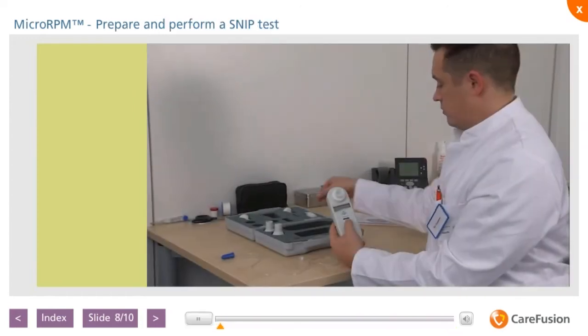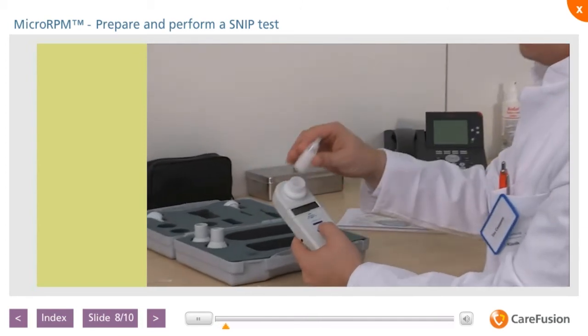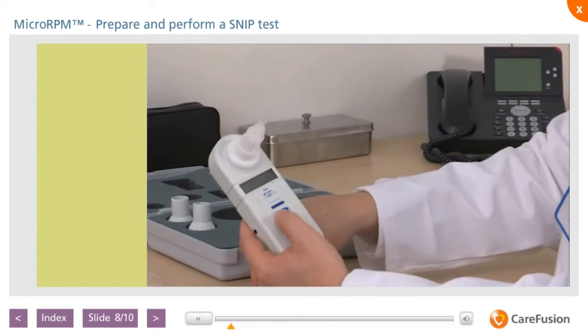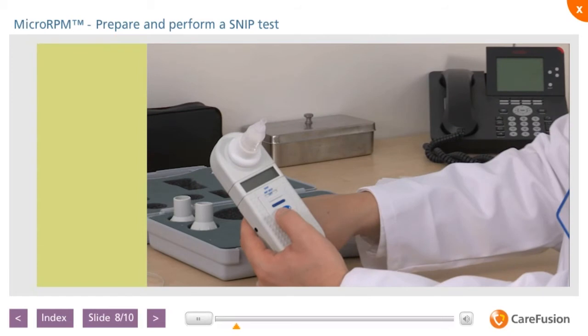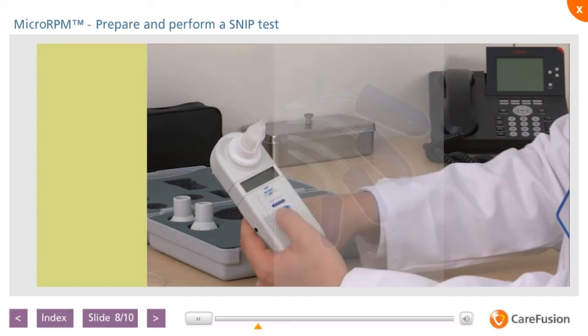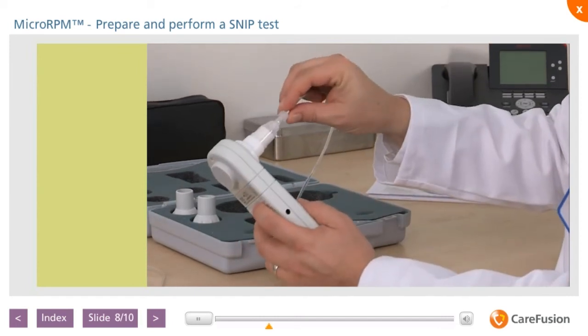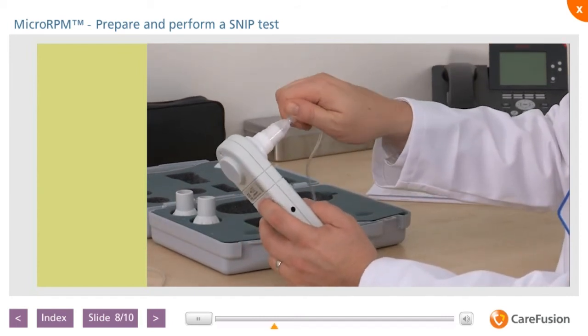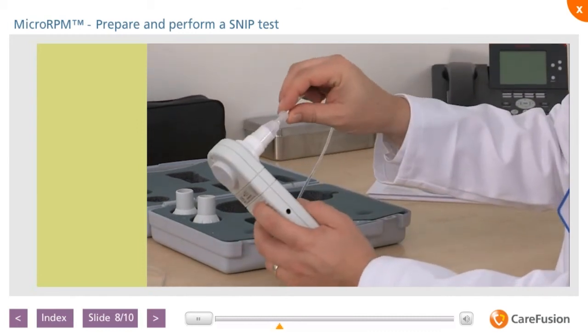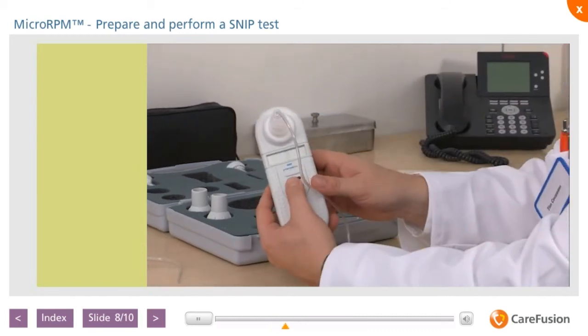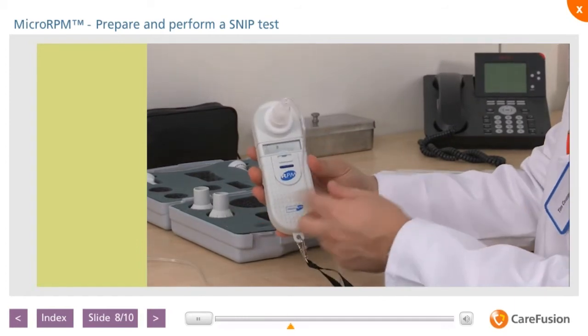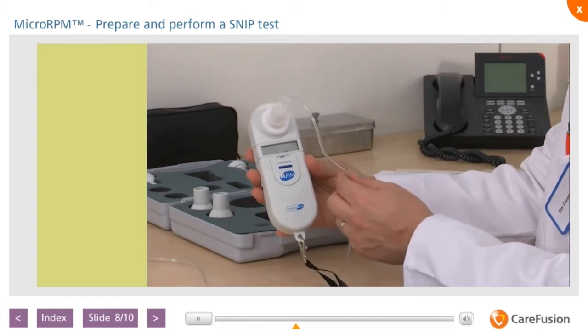With the unit turned off, connect the nasal probe adapter to the MicroRPM. The nasal probes used for performing a SNIP maneuver are supplied in 4 sizes: extra small, small, medium and large. Select the appropriate size to ensure a tight fit in the patient's nostril. Attach the chosen nasal probe to the probe adapter using the luer fitting, twisting it as you attach it to the adapter.